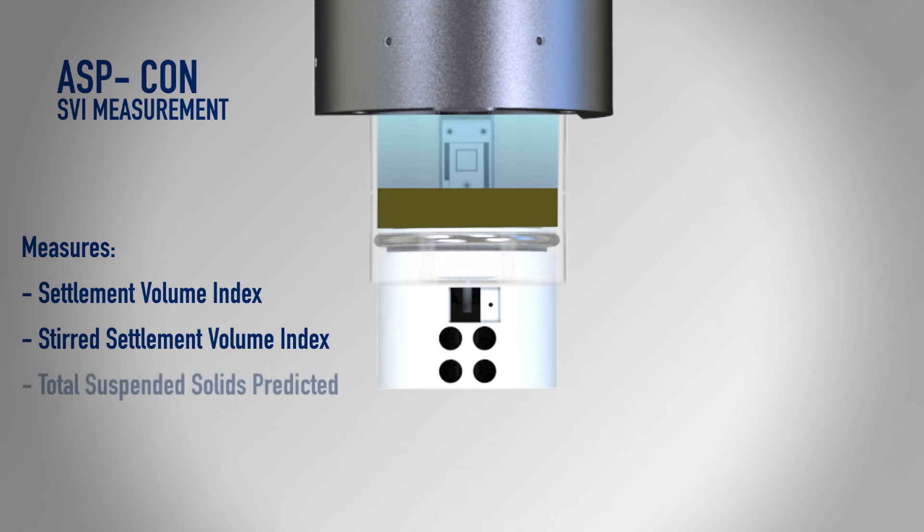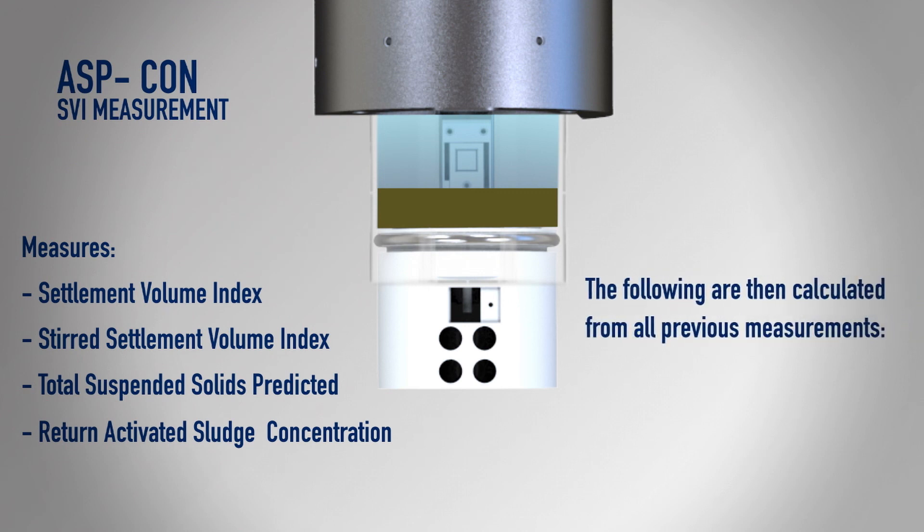The sensors measure the turbidity of each part of the sample and also the settlement volume index, stirred settlement volume index, total suspended solids predicted, return activated sludge concentration, and the following are then calculated from the previous measurements food to mass ratio and toxicity.